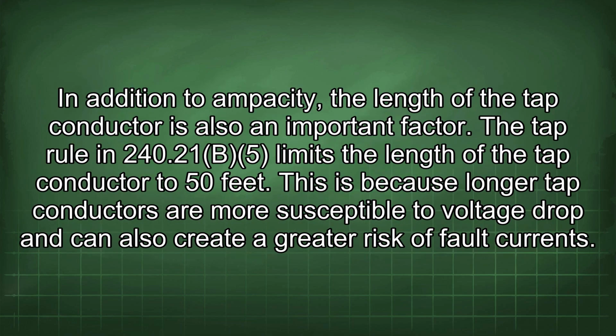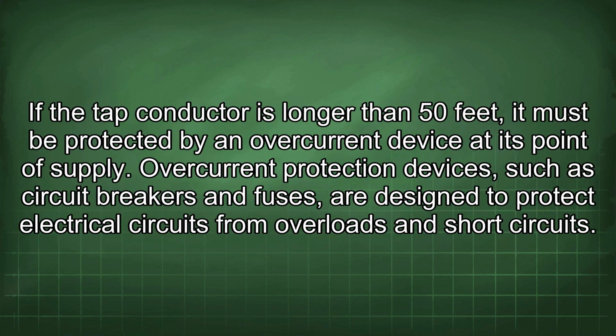In addition to ampacity, the length of the tap conductor is also an important factor. The tap rule in 240.21(B)(5) limits the length of the tap conductor to 50 feet. This is because longer tap conductors are more susceptible to voltage drop and can also create a greater risk of fault currents. If the tap conductor is longer than 50 feet, it must be protected by an overcurrent device at its point of supply.